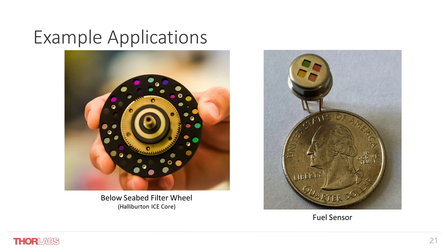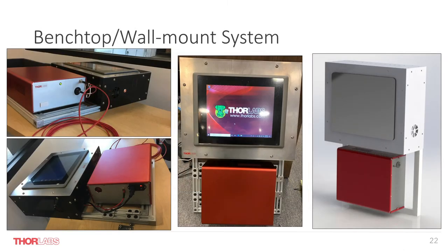Before I started working on this project, I had no idea how much variability there was with the efficiency values in fuel and gases. A spectrometer could have done the job, but you just cannot easily stick a delicate spectrometer in a fuel line of a vehicle for several reasons: physical size, speed of the output, and of course weight and cost. Here we have a system we developed for one of our industrial customers. This system is quite similar to the demo I just walked you through. However, we were able to reduce the footprint, make it wall mountable, and provide a nice touch screen and user display at the request of the customer. This particular system was designed to measure a chemical process in real time and in line. The enclosure could have easily been ruggedized or explosion-proof if that had been required by the customer.